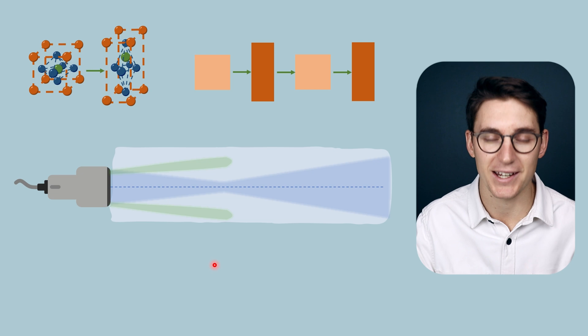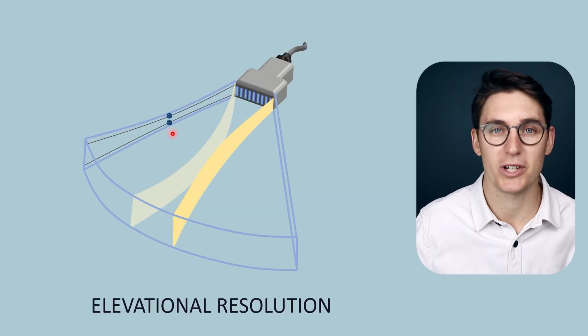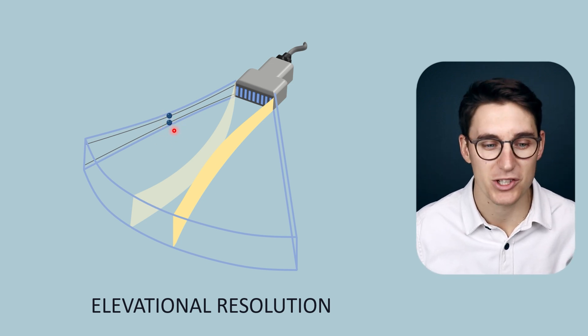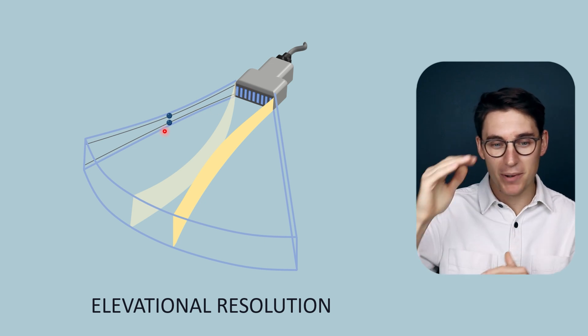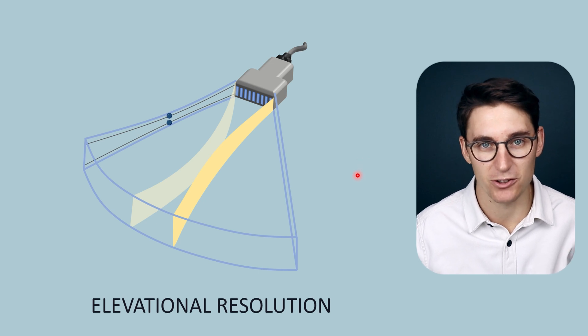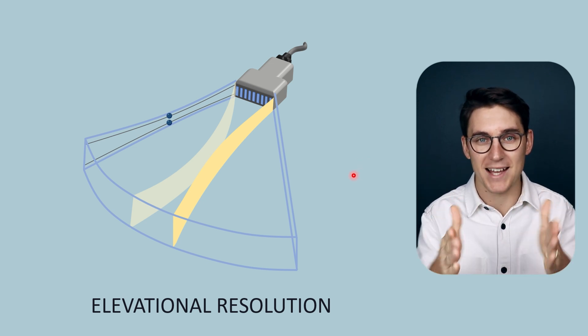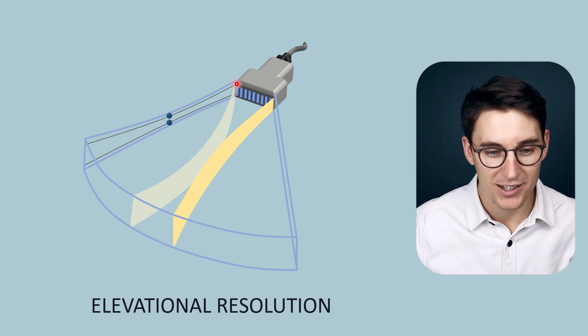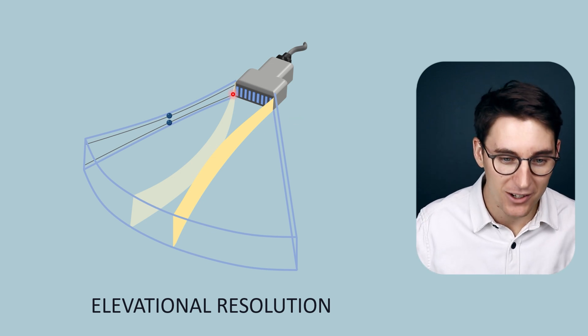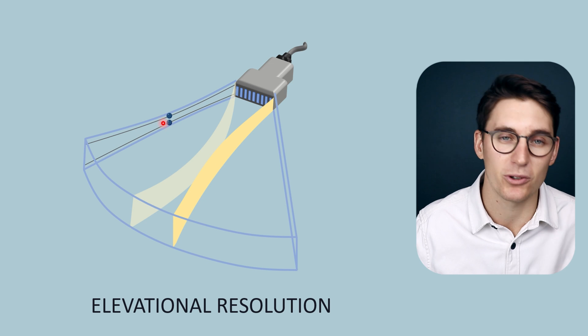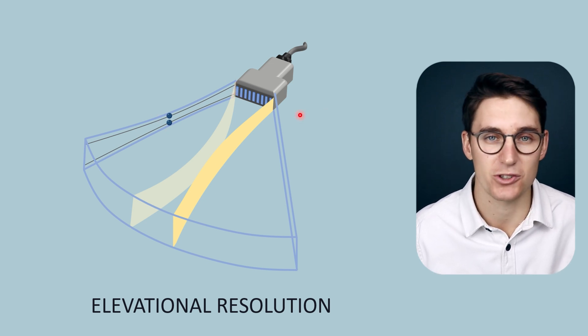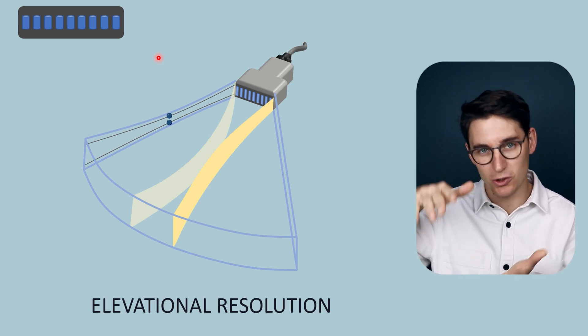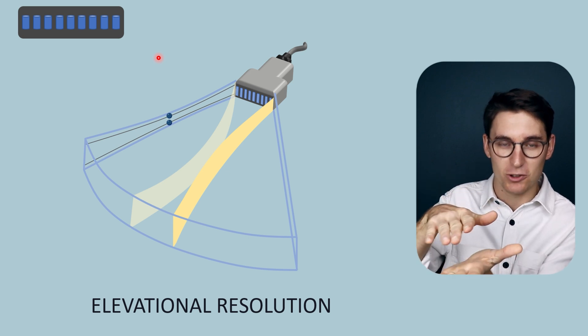Let's briefly look at elevational resolution. Elevational resolution refers to differentiating two discrete objects in the elevational or height plane — they are at the same depth but in a different z-plane. Elevational resolution is much like lateral resolution: lateral resolution relates to beam width, while elevational resolution relates to beam height as it heads into tissue. Much like beam width narrows at a focal zone, the elevational height also narrows at a focal point, and this is dependent on the height of the transducer elements.